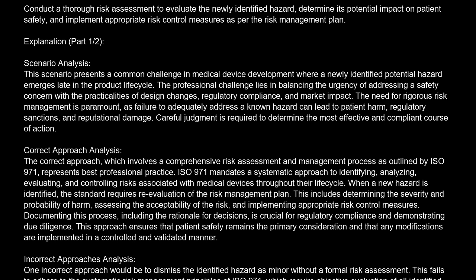Correct approach analysis. The correct approach, which involves a comprehensive risk assessment and management process as outlined by ISO 14971, represents best professional practice. ISO 14971 mandates a systematic approach to identifying, analyzing, evaluating, and controlling risks associated with medical devices throughout their life cycle. When a new hazard is identified, the standard requires re-evaluation of the risk management plan.